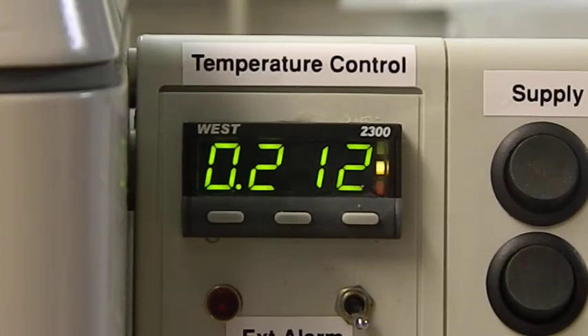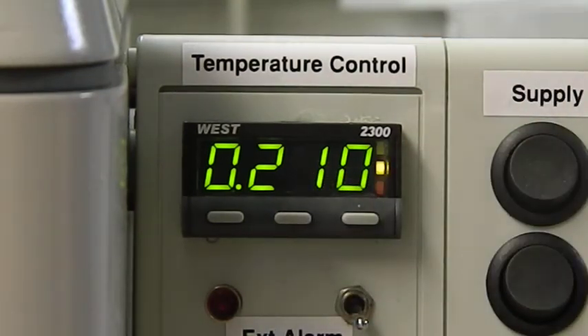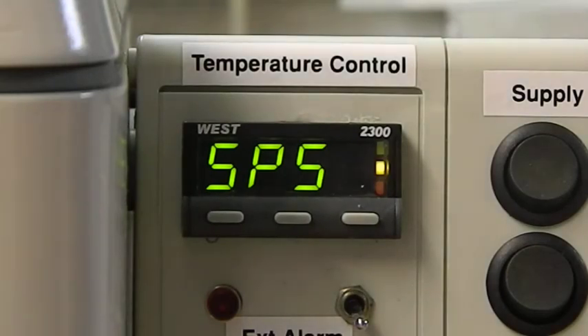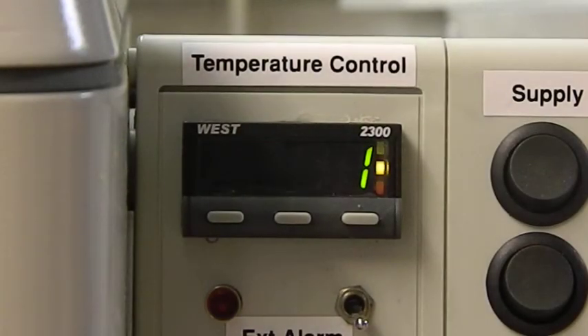0.212, this particular setting is used for the USB version of the machine, which we'll cover in a different video. So I'm actually going to take this down to 210, which is the correct setting for a standard Mark 6 professional machine without USB connections. Press it twice again to get to SPS. This is a parameter that we use, and the setting must always be 1.